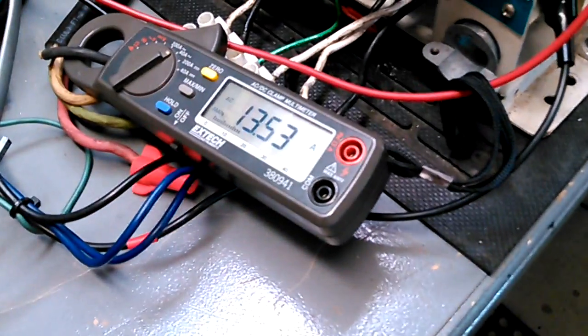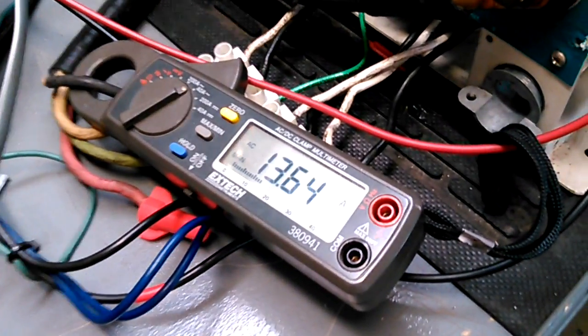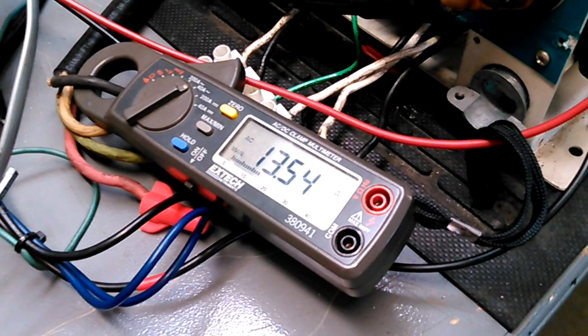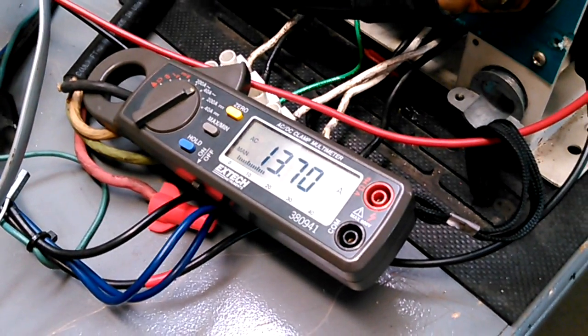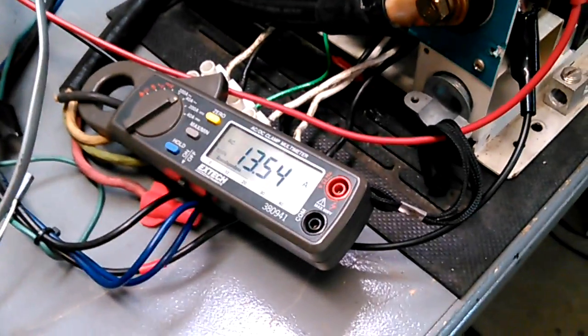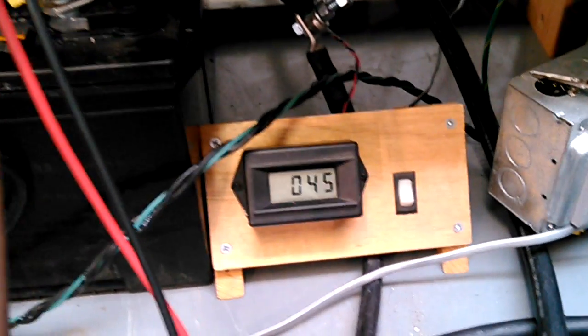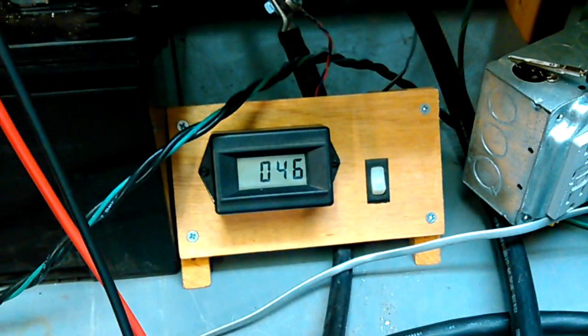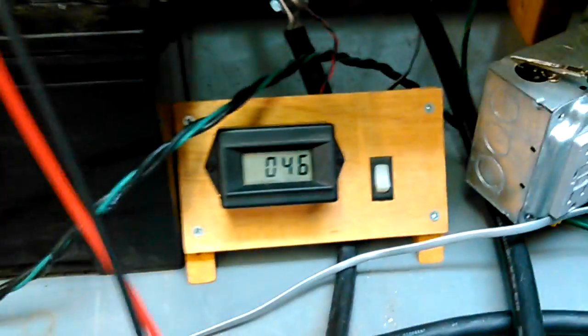Your charger's only pumping 45 amps instead of 100 amps into your batteries. But look how much current I saved here. Now I'm only pulling 13 amps from shore power instead of 22 amps. And that gives me more room to turn more things on if I need to. And if you're plugged in all day long, there's plenty of time at 45 amps to get those batteries charged up.